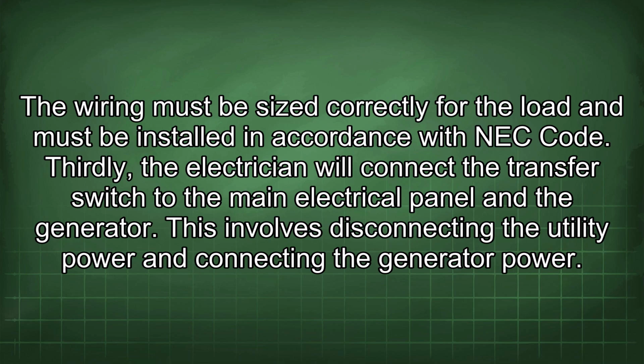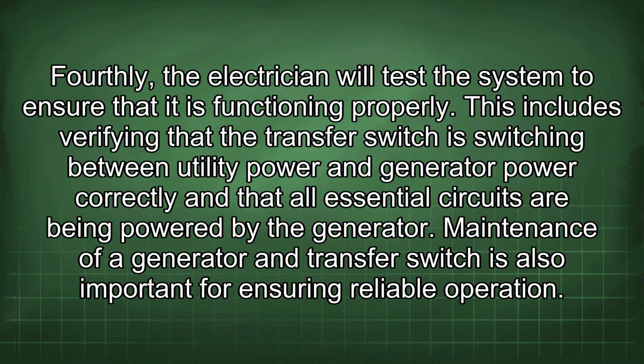Thirdly, the electrician will connect the transfer switch to the main electrical panel and the generator. This involves disconnecting the utility power and connecting the generator power. Fourthly, the electrician will test the system to ensure that it is functioning properly. This includes verifying that the transfer switch is switching between utility power and generator power correctly and that all essential circuits are being powered by the generator.